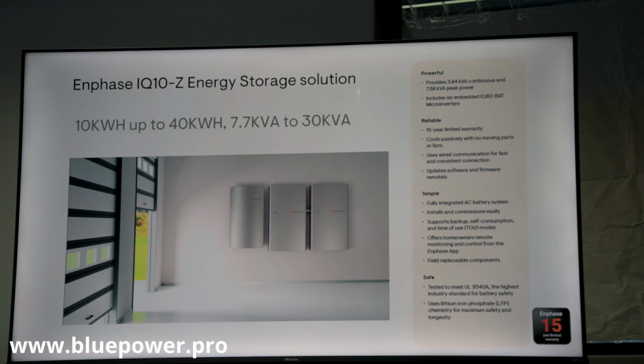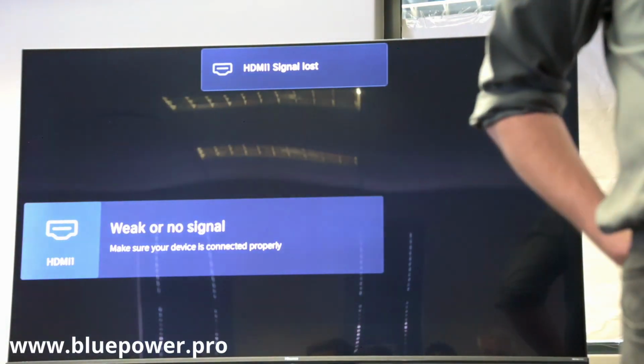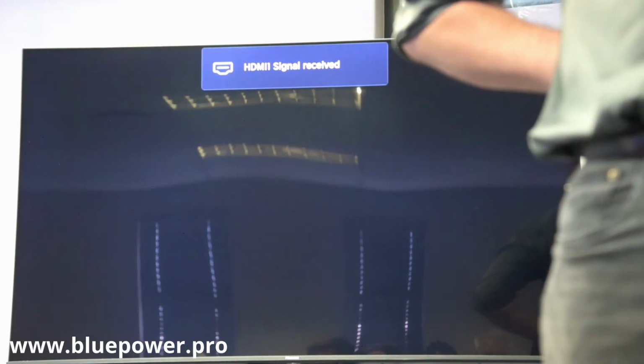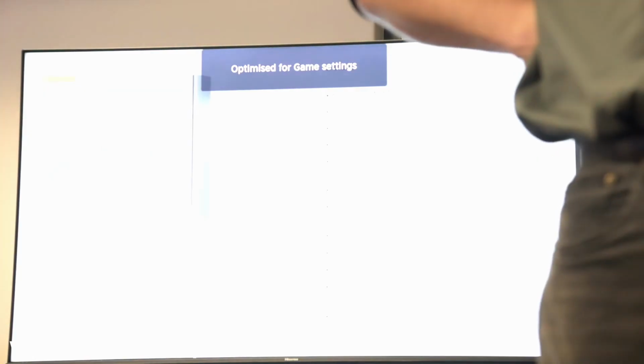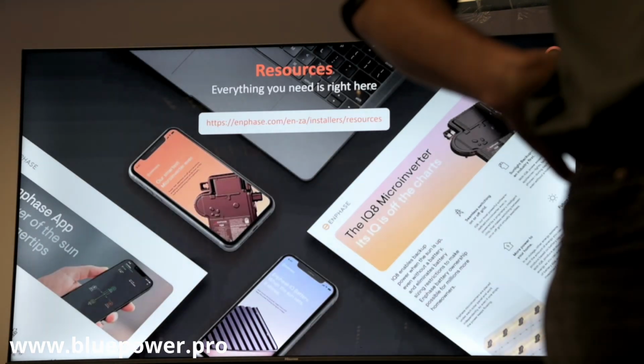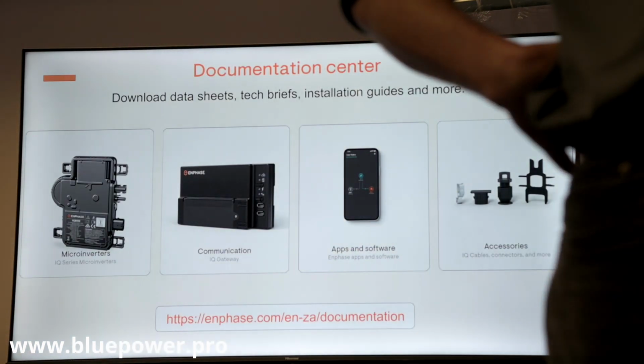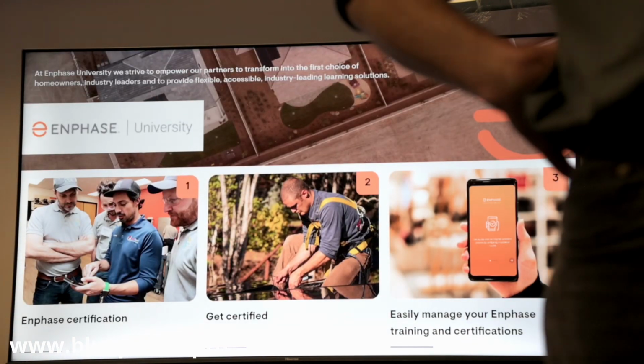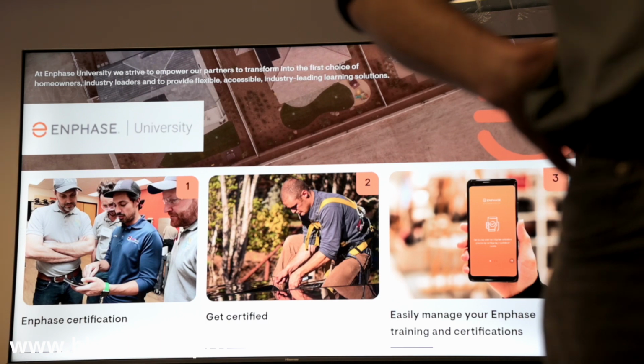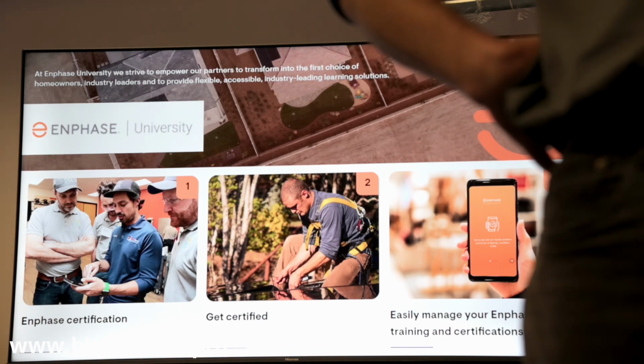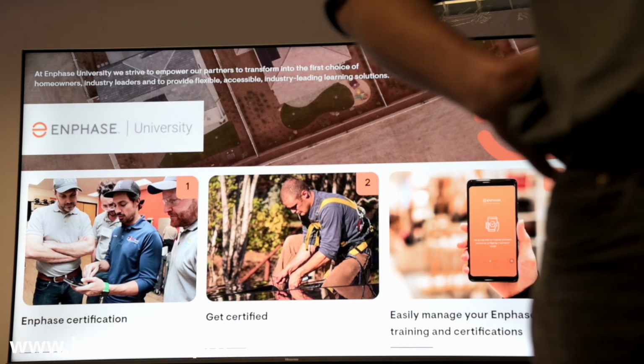So you're mentioning that product can plug in at any point. If you have an existing off-grid backup system with a changeover switch, running on your essential loads—yes—then essentially it has to have sufficient cable size. There's no point putting it onto a 16 amp phase and trying to feed 50 amps back along the line. So you're saying you can add it at a point near the roof as long as you have sufficient capacity on the cable between there. That's about right.